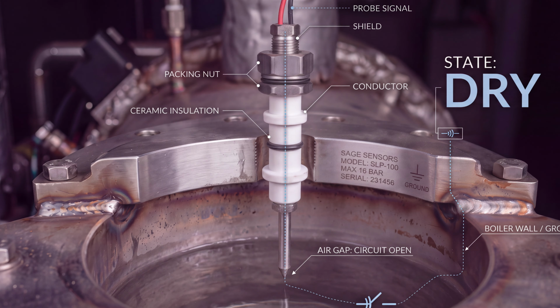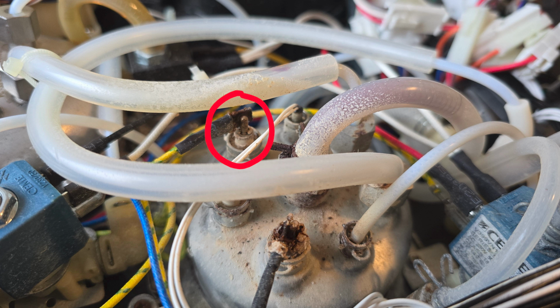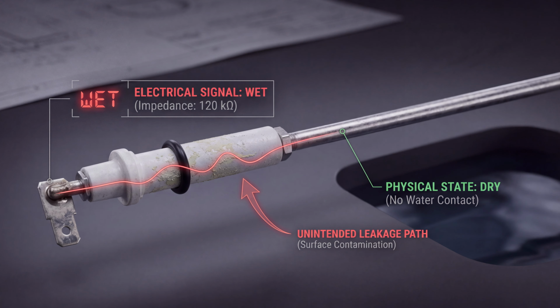But there's one weakness in this system. The machine doesn't actually know whether the probe is touching water. It only knows what the electrical signal tells it. After years inside a steam boiler, these probes are exposed to heat, steam, condensation, and minerals. Deposits and contamination can build up around the probe and its insulating surface. You don't need a complete short circuit. You only need enough electrical leakage for the electronics to interpret the signal incorrectly. So now you can have a probe that is physically dry, while electrically, the machine still sees wet.